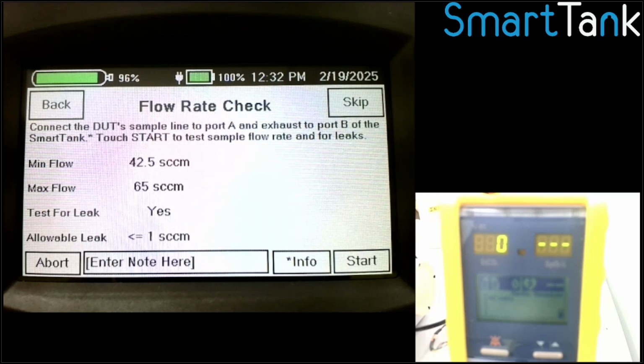Now, let's say though, in your facility, you always want to recalibrate it. Again, we can tweak the sequences to force somebody to go through that calibration if that's something you want to do. So now we're on step 2. This is the second test in this little sequence. We're going to check the flow rate.